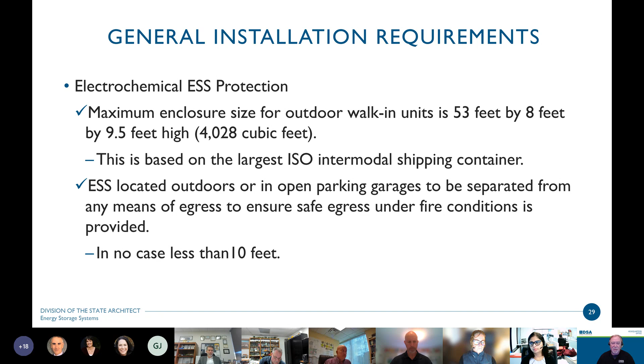ESS located outdoors or in open parking garages need to be separated from any means of egress. Obviously, this is to ensure safe egress under fire conditions, and in no case less than 10 feet from buildings. Placement of the units outdoors certainly shouldn't be impeding or impacting any adjacent egress from school buildings.